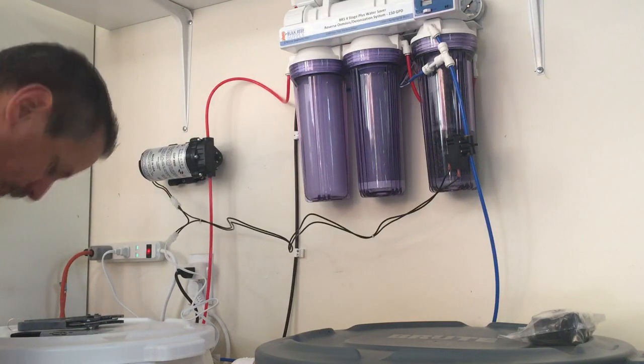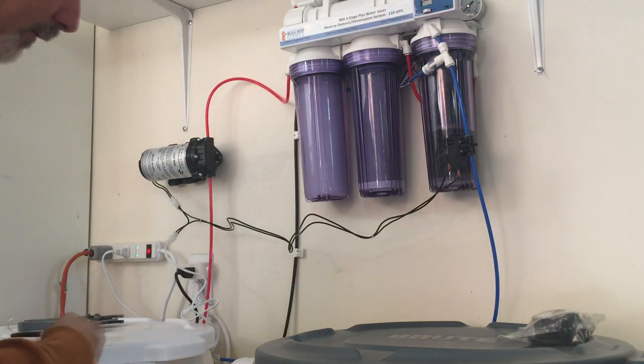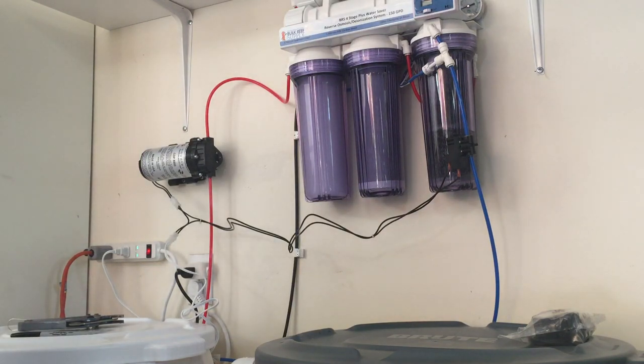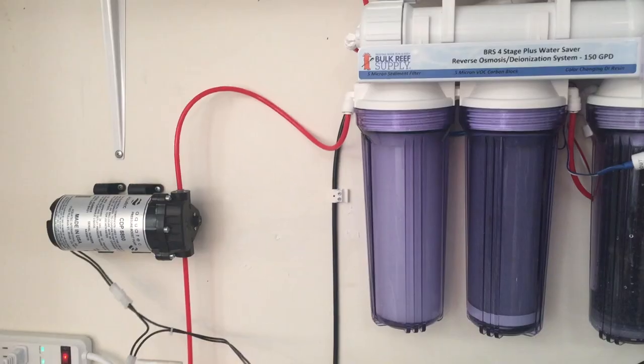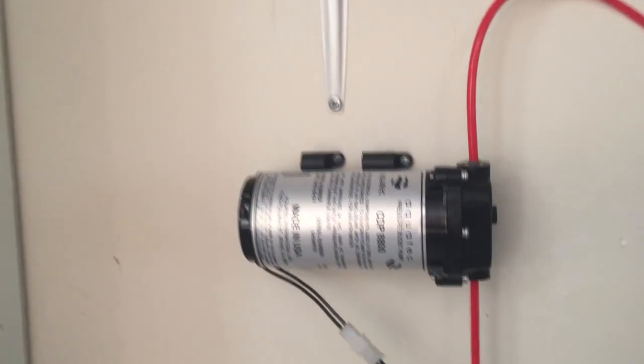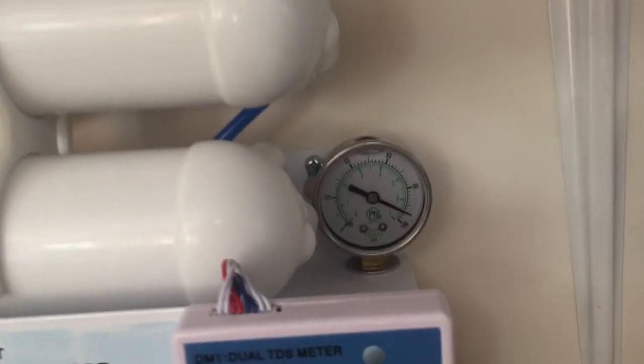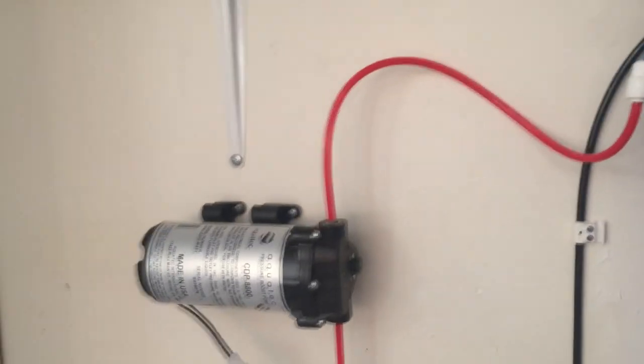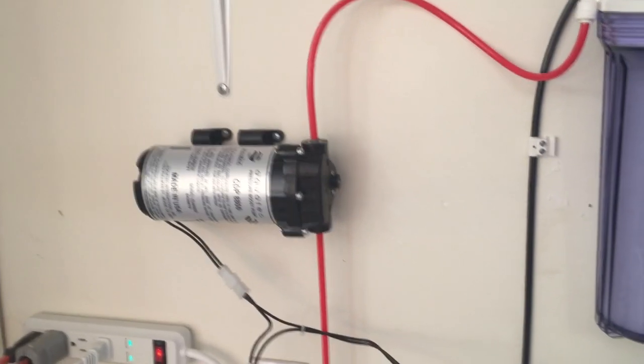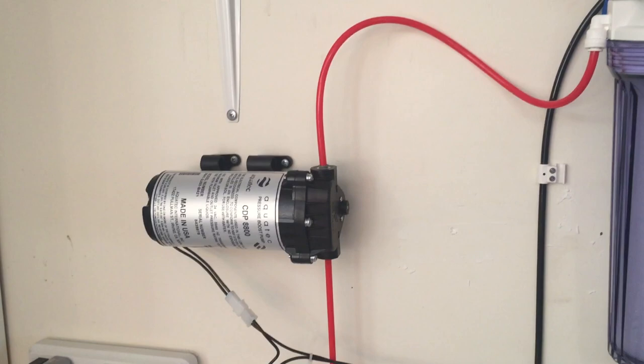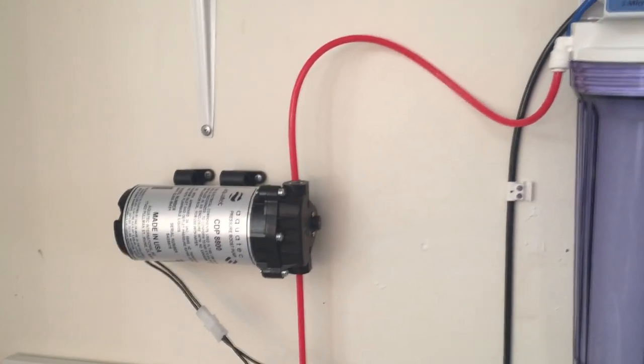I'm going to turn your water supply on. Remember I put the little valves on there to turn it on. So I have the water supply going through now. You can hear the pump's on. You see it vibrates a little bit. But like I said, that's why they have the flexible mounts. The water pressure is just above 90, about 95, which is still a little too high. There is an adjustment on here that we'll make. You can turn it down. It can only go down.